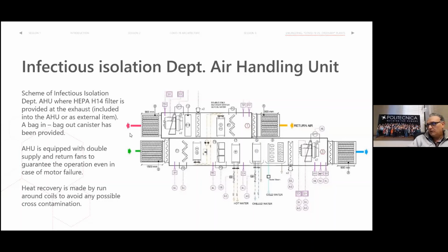It is important to have here, where there is this filter, which is the most important, the most dangerous part of this unit, a bag-in, bag-out canister, to have a safe substitution of the filter. So it is not just like a normal filter. We must have a system where you push the filter from one side and you put it in a bag on the other side without touching it with your hands. And so then you substitute it with a new one, which is of course not dangerous because it is still clean.